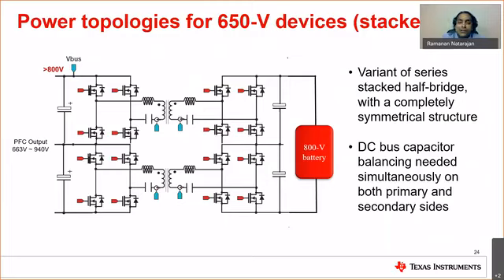Here is another variant of the stacked half-bridge arrangement, with a more symmetrical structure with a split DC capacitor on both the primary and secondary side. This enables the use of a more traditional full bridge structure on the primary and secondary, with the transformer connected in between, simplifying the overall arrangement. However, there's the additional task of achieving simultaneous balancing of the capacitor voltages on both the secondary and primary sides.